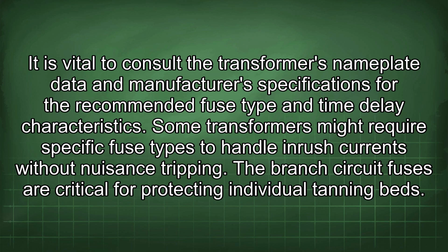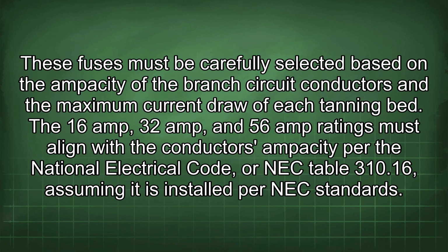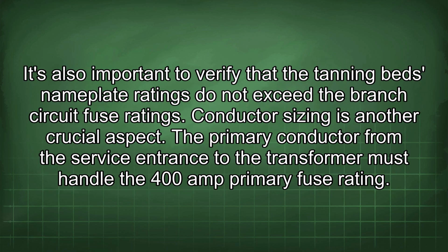The branch circuit fuses are critical for protecting individual tanning beds. These fuses must be carefully selected based on the ampacity of the branch circuit conductors and the maximum current draw of each tanning bed. The 16 amp, 32 amp, and 56 amp ratings must align with the conductor's ampacity per the National Electrical Code, or NEC Table 310.16, assuming it is installed per NEC standards. It's also important to verify that the tanning bed's nameplate ratings do not exceed the branch circuit fuse ratings.